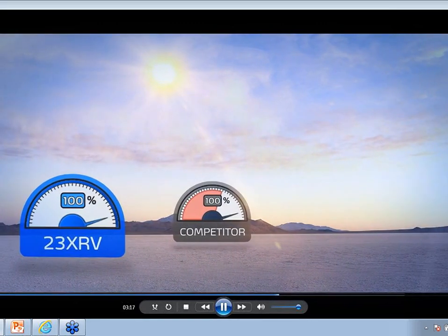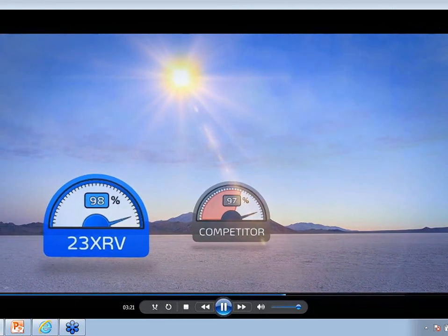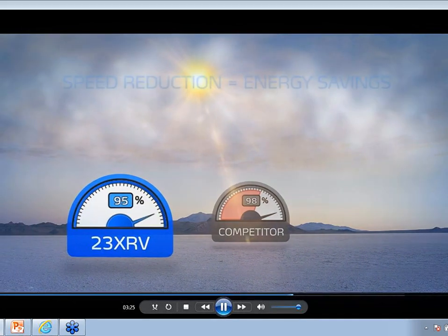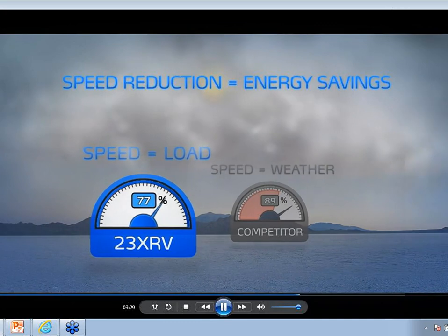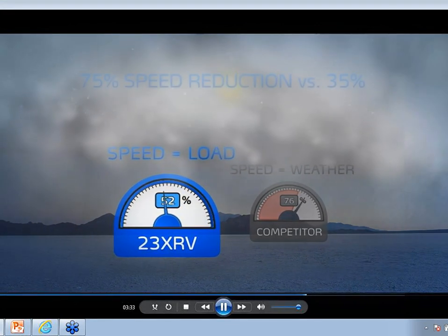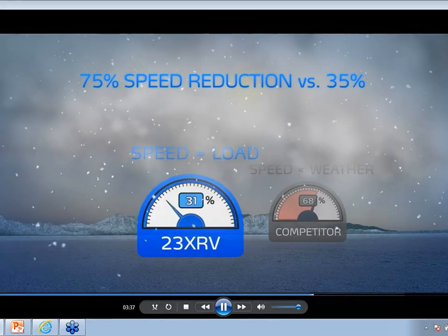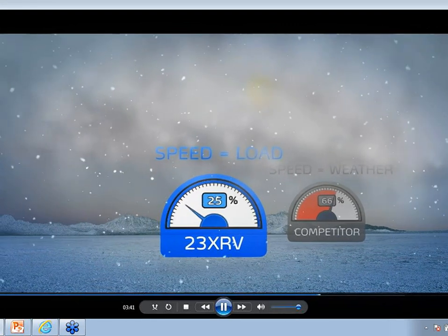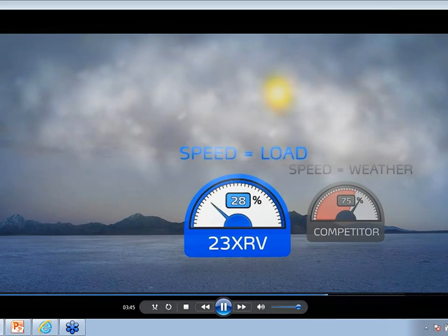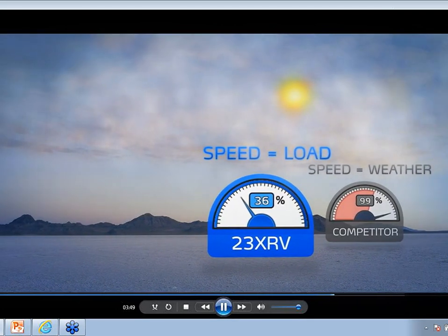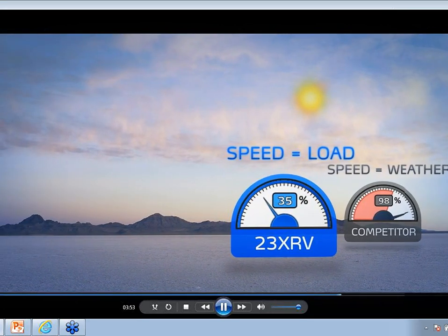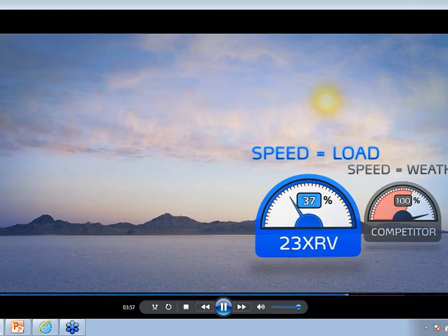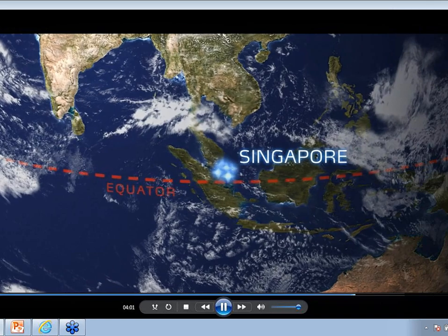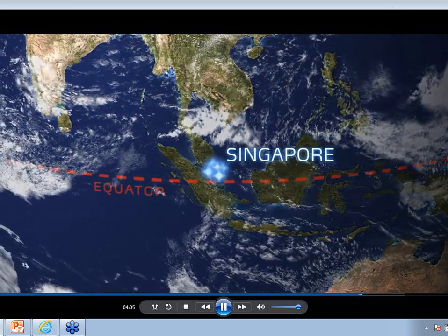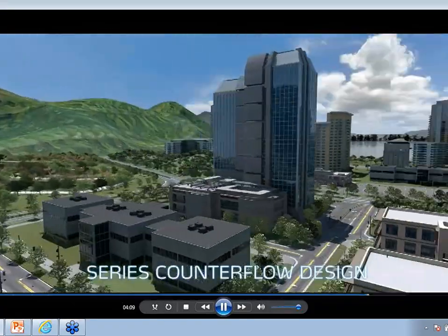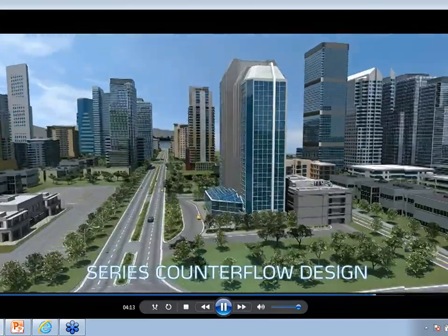This inherent advantage in compression technology provides confidence in an imperfect world and delivers another striking advantage over other technologies: more speed reduction. And as we all know, more speed reduction means more energy savings. The 23XRV can achieve 75% speed reduction versus just 35% for centrifugal compressors. In addition, centrifugal speed is a function of load and weather. Warm weather can limit centrifugal speed reduction and energy savings potential. In contrast, 23XRV speed precisely tracks capacity, so load reductions are matched by energy-saving speed reduction in any climate. The Carrier 23XRV chiller is used due to its efficiency. It was in line with our direction for Green Mark Platinum Award. The initial target was to achieve 40% electrical savings on the chiller plant system. Currently, we are already close to hitting the target.